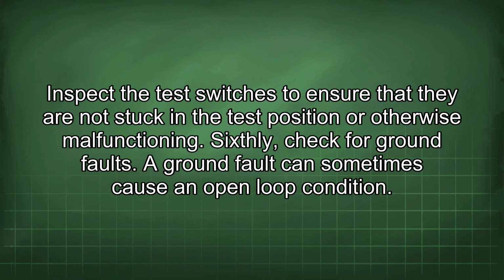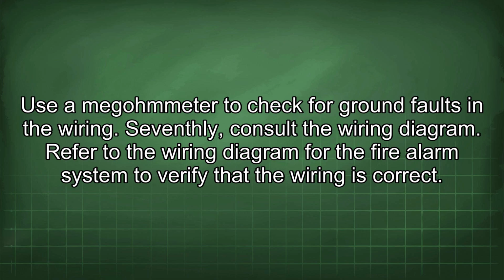Sixthly, check for ground faults. A ground fault can sometimes cause an open loop condition. Use a megohmmeter to check for ground faults in the wiring.